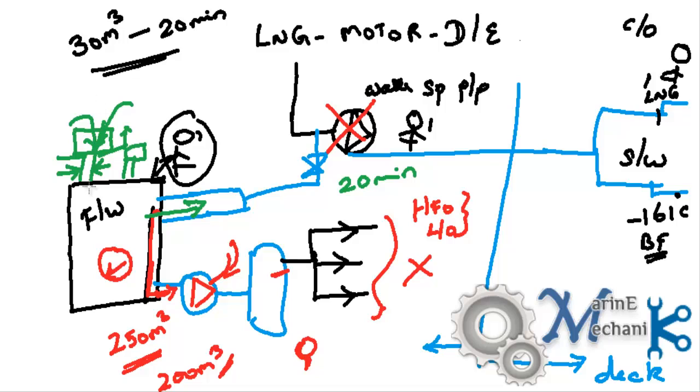We managed to open the vent head and then air was rushing in. Finally after 10 to 15 minutes, everything solved out. The water level gauge showed suddenly a reading. The water level of the tank was coming up. We purged out the hydrophore pump, pressurized the hydrophore tank, and then water went to accommodation.